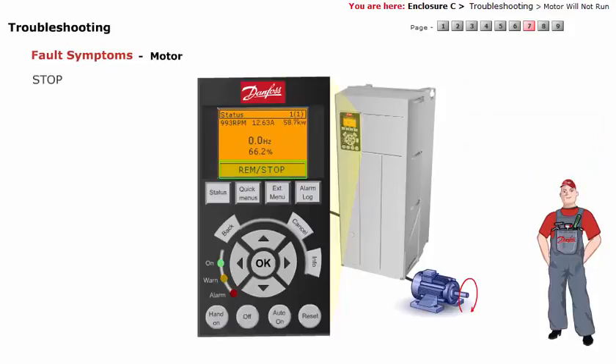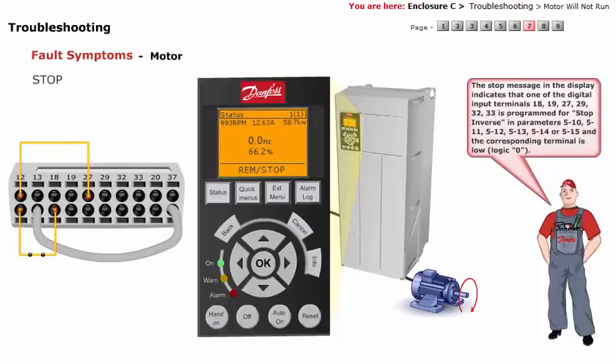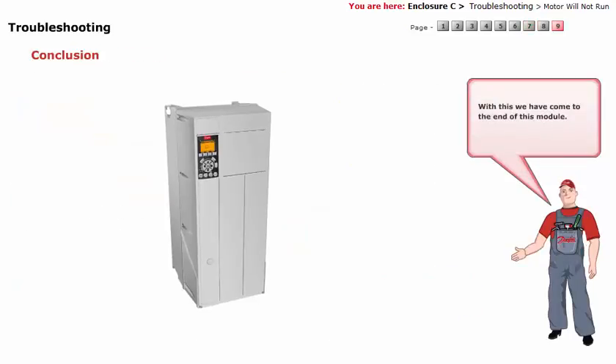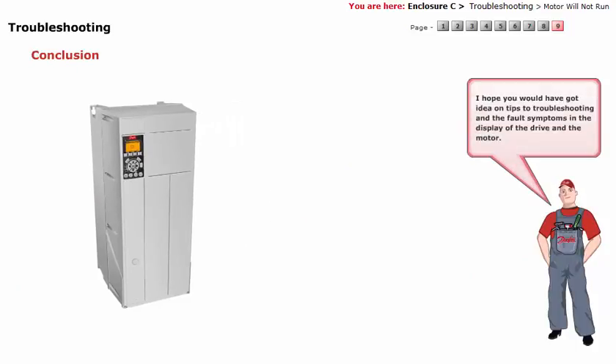Stop Stop: The stop message in the display indicates that one of the digital input terminals 18, 19, 27, 29, 32, or 33 is programmed for stop inverse in parameters 510, 511, 512, 513, 514, or 515, and the corresponding terminal is low — logic 0. With this, we have come to the end of this module. I hope you have gained an understanding of troubleshooting tips and fault symptoms in the display of the drive and the motor.